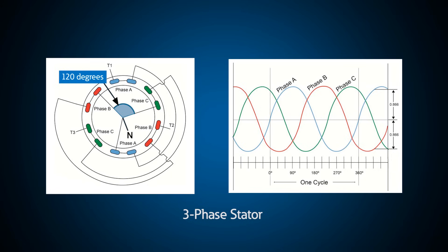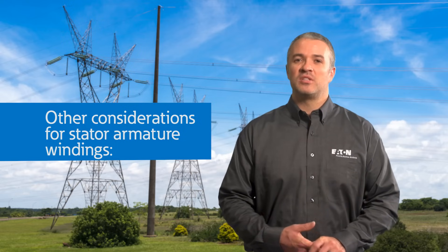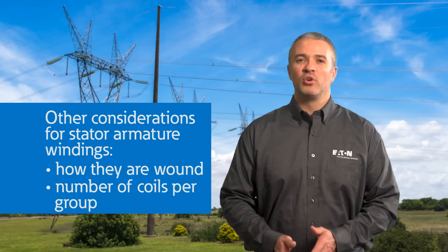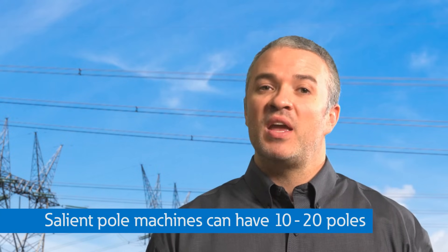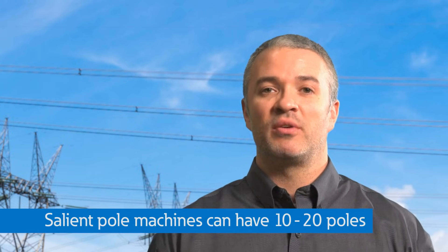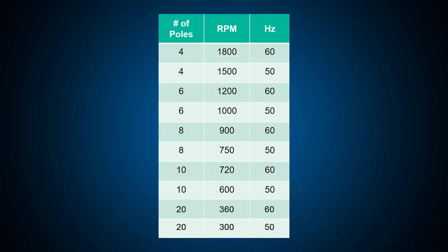As the rotor spins, three separate voltages are created at the stator terminals. The frequency of a generator is directly related to the number of poles on the rotor and the speed at which it spins. For example, for a four-pole rotor to rotate at 60 Hertz, it would have to spin five times faster than a 20-pole rotor, putting much more mechanical stress on the generator. Salient pole machines may have 10 to 20 poles, reducing the stress but running at a lower RPM. Power plants may choose a rotor with a certain number of poles depending on the speed needed for the application.